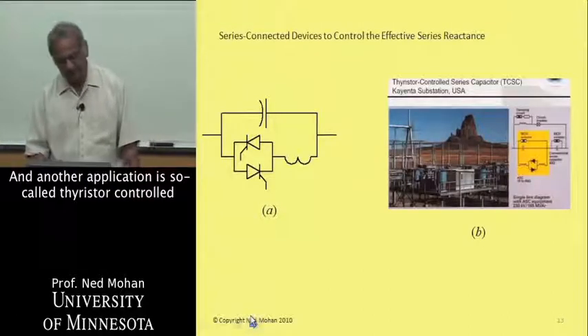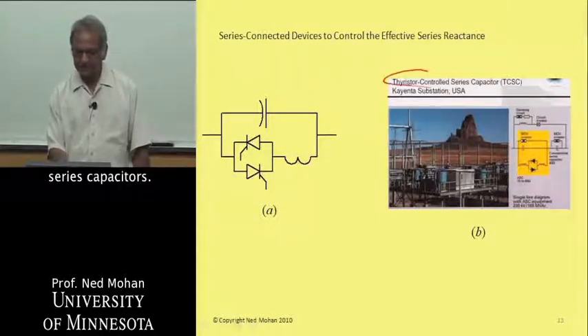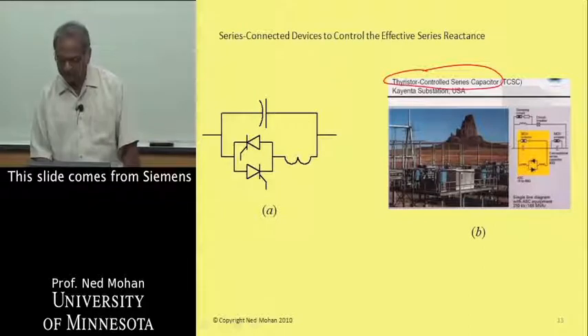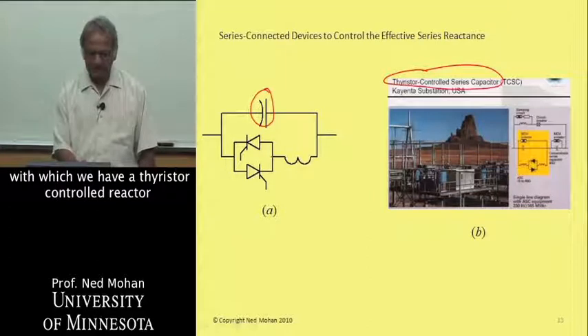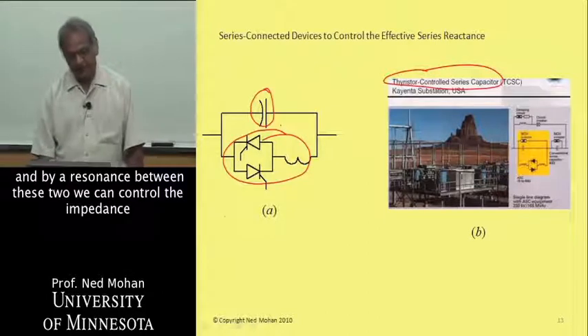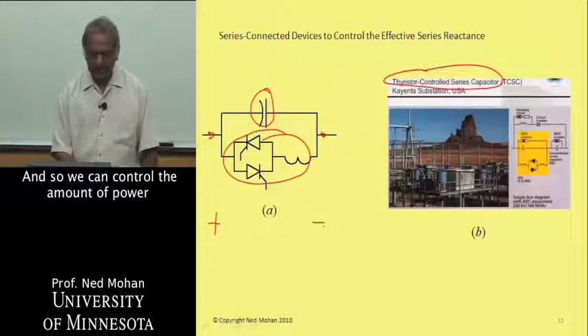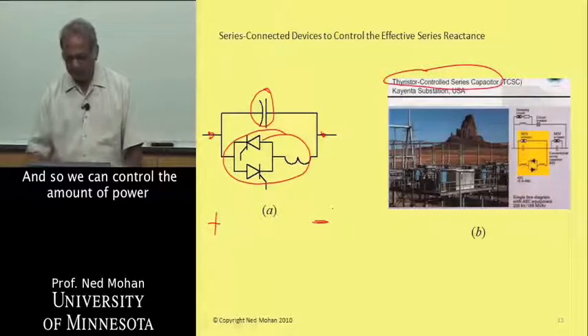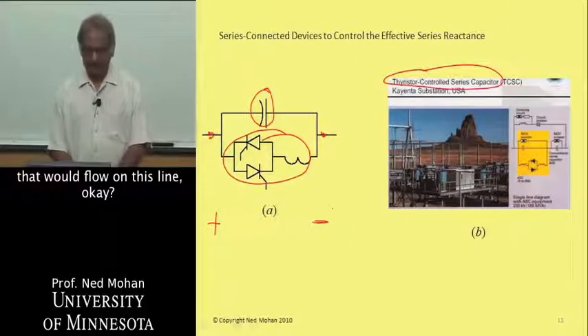Another application is thyristor-controlled series capacitors, or TCSC. This slide from Siemens shows a capacitor in parallel with a thyristor-controlled reactor. By resonance between these two, we can control the impedance between these two points, and thus control the amount of power that flows on this line.